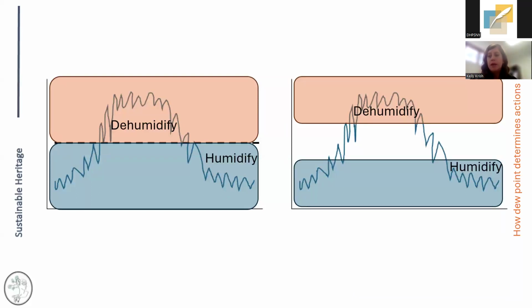Okay, so when it comes to determining set points, I wanted to go back to the graph a little bit. Both of these are meant to show your outside air dew point. If you then draw an invisible line or a real line on your graph for the dew point that you're locked into, any point above there is when you're going to need to dehumidify. You're going to have to remove moisture to get it back down to that line. And at any point below that line, you're going to have to be humidifying to bring it up to that line. This can be really helpful to visualize, because you can see in the graph on the left, nearly throughout the whole year, I have to do some work mechanically in order to meet my set point. I'm always asking the system to do something.